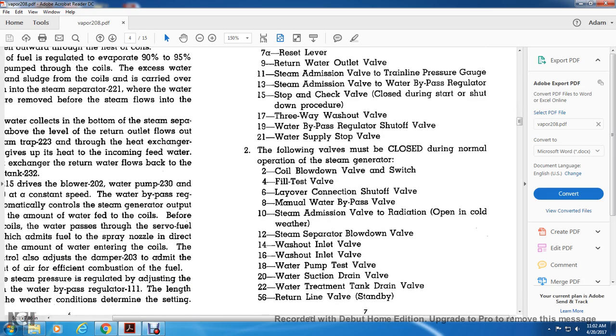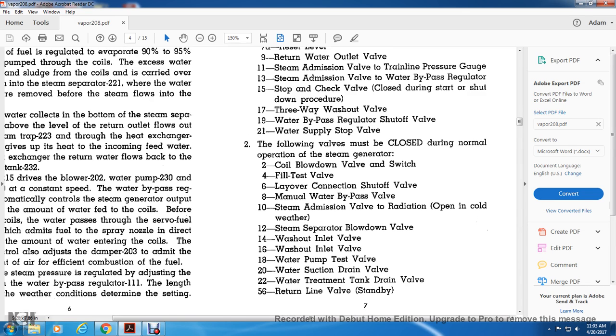The following valves must be closed during normal operation of the steam generator. 2, the coil blowdown valve. 4, the fill test valve. 6, the layover connection shutoff valve. 8, the manual water bypass valve. 10, the steam admission valve to the radiation, opened in cold weather. 12, the steam separator blowdown valve. 14, the washout inlet valve. 16, the washout inlet valve. 18, the water pump test valve. 20, the water suction drain valve. 22, the water treatment drain valve. And 56, the return line valve standby.